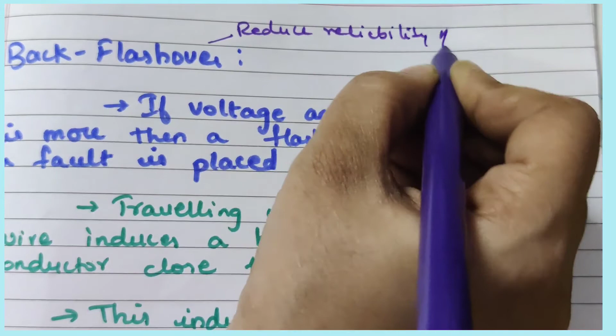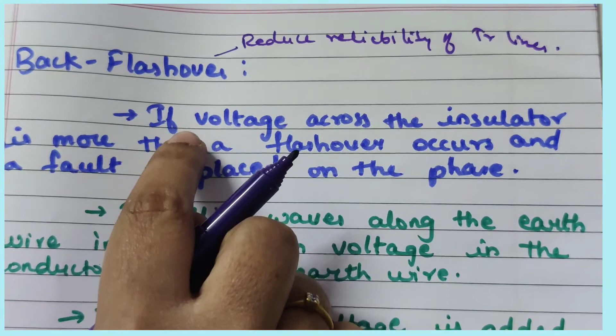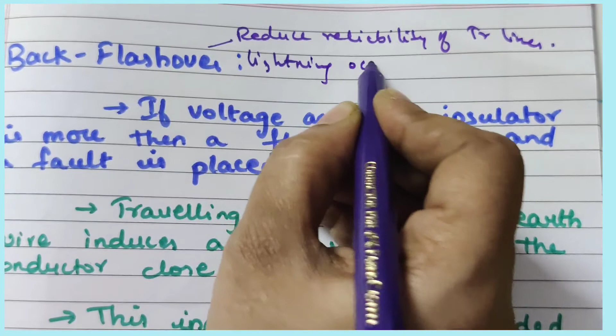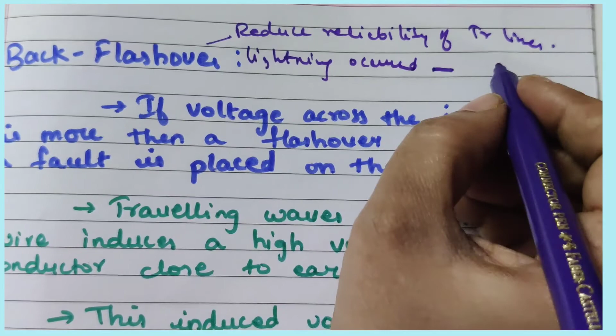To be clear, flashover reduces the reliability of transmission lines. If there is a direct lightning stroke to the tower structure or any guard wires, it will inject some wave currents into the earth wire we are using.